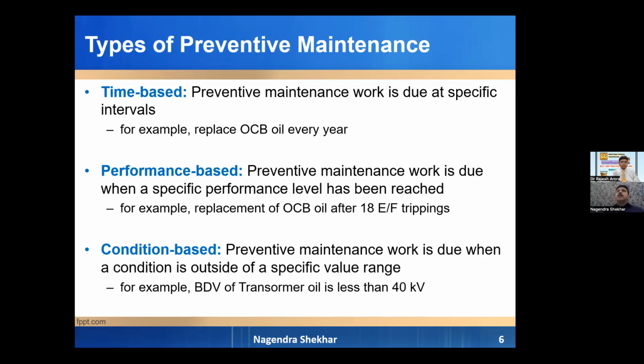Predictive maintenance is something when neither is it scheduled nor is there a breakdown, but something is noticed which may result in a breakdown, like partial discharge. Nowadays the technology has come where, without putting off the power supply, you detect the sound of sparking or tracking. That sound will indicate in how many days a fault will develop. So accordingly you can plan. So this is predictive maintenance, condition based maintenance. Similar kind of maintenance is thermoscanning. When you thermoscan connectors, connections, and you find unusual heat on particular connections, you take action accordingly. So these are the condition based or predictive maintenance.